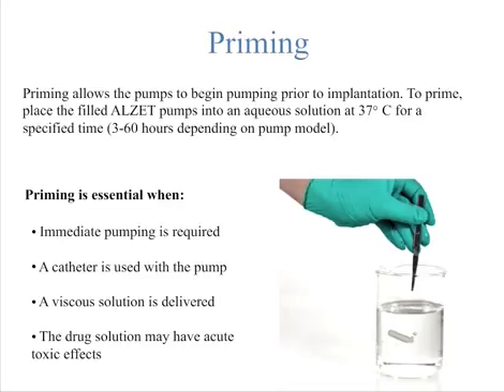Now, there's only 4 reasons why you would want to prime the pump before you implant it. And it's listed there. 1, like I mentioned, if immediate pumping is required. 2, if a catheter is used with the pump. 3, if a viscous solution is being delivered. And 4, if the drug solution may have acute toxic effects.